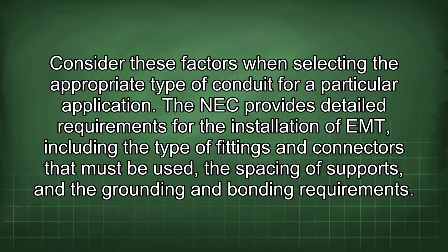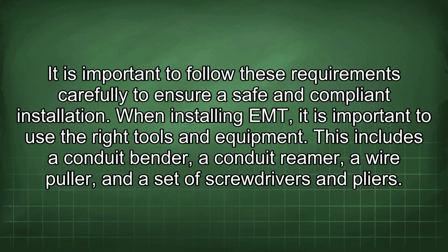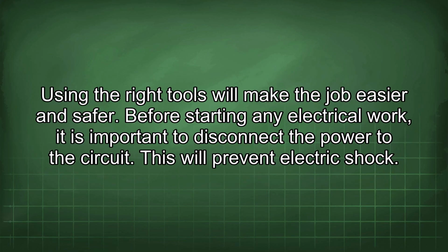The NEC provides detailed requirements for the installation of EMT, including the type of fittings and connectors that must be used, the spacing of supports, and the grounding and bonding requirements. It is important to follow these requirements carefully to ensure a safe and compliant installation. When installing EMT, it is important to use the right tools and equipment. This includes a conduit bender, a conduit reamer, a wire puller, and a set of screwdrivers and pliers. Using the right tools will make the job easier and safer.